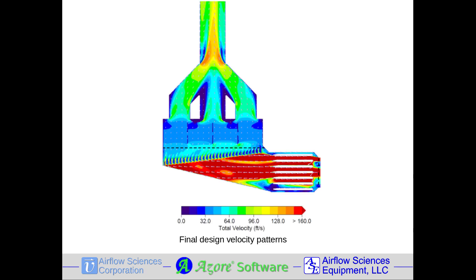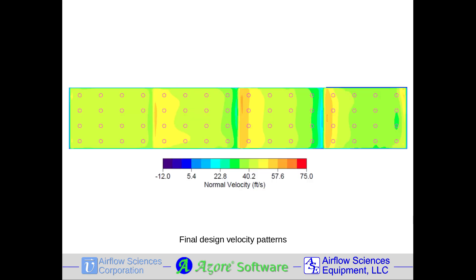These design changes resulted in a flow field that achieved both uniform and aligned flow entering the tube bank region. The resultant CFD flow profile upstream of the tube bank eliminated the higher velocities and reduced the RMS from 28% down to 11%, achieving project goals.